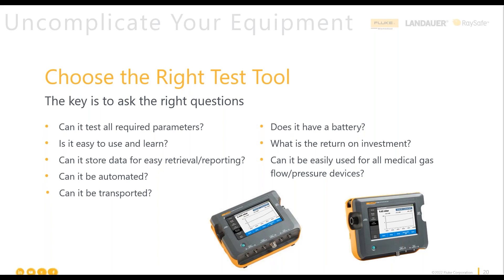Think about what other medical gas flow testing needs the gas flow analyzer could fulfill. Does it have integrated DPM — digital pressure meter functionality? Does it compensate for temperature, humidity, and pressure so you don't have to? These are all great questions to consider because the analyzer doesn't just have to be a ventilator tester — it really can be a full gas flow analyzer. This lets you carry less to the job and ultimately do less while you're there. Think about those economic efficiencies: a shorter learning curve, better ROI, and shorter time to break even.